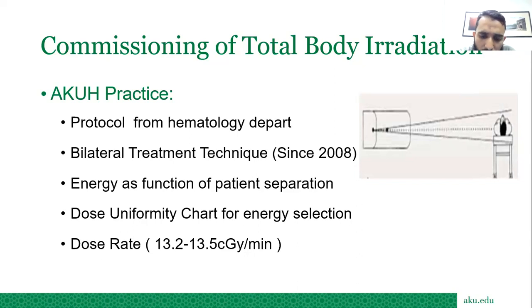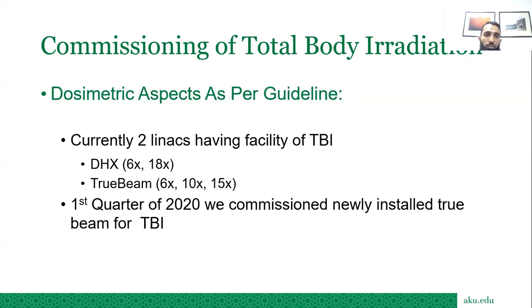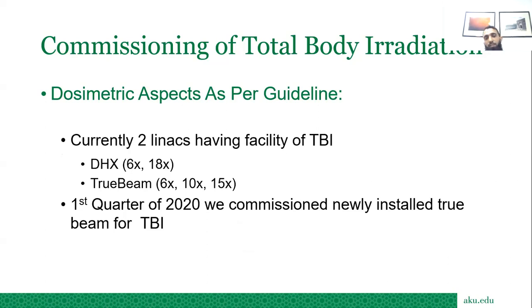Literature suggests the dose rate should be low — 15 cGy/min or less than 10 cGy/min — to reduce chances of rejection in stem cell grafting. We have two linacs: DHX with 6X and 18X energies, and a TrueBeam with 6X, 10X, and 15X energies. My presentation covers TrueBeam commissioning done in the first quarter of 2020.